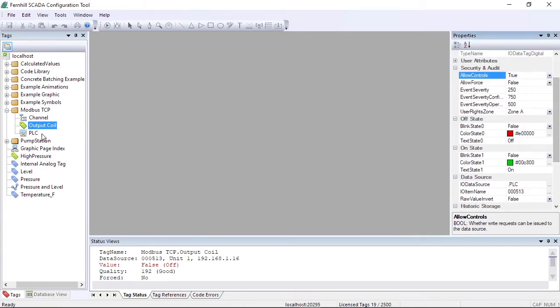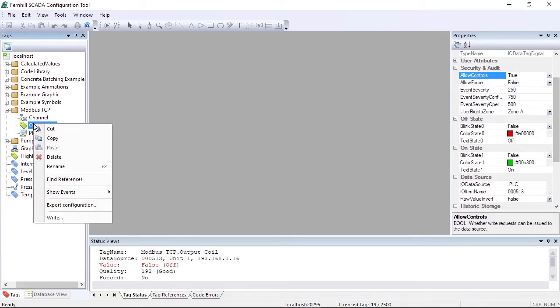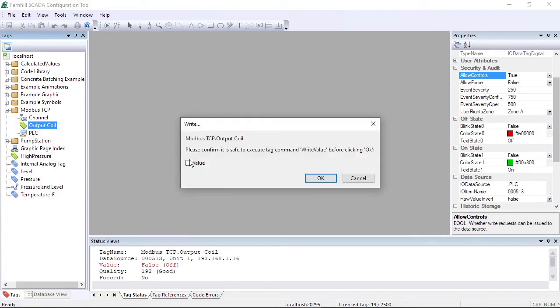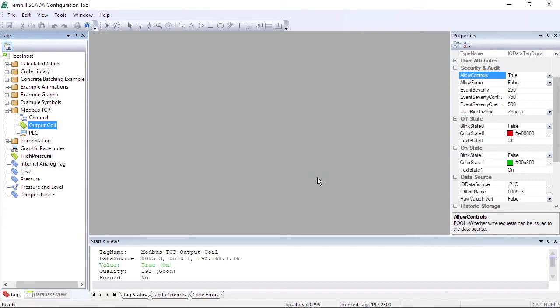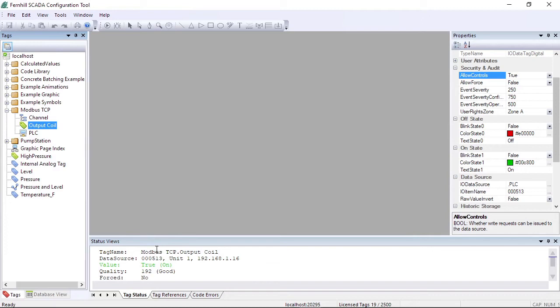Now, when we right click on the IO data point tag in the tag window, we get an option to write a value. We can use this option to send a write request to the PLC. When we click OK, Fernhill SCADA will send a write coil command to the Modbus device. In the tag status window, we can see the tag has changed state to reflect the new state of the Modbus coil.